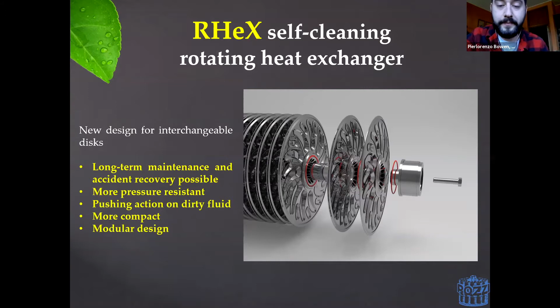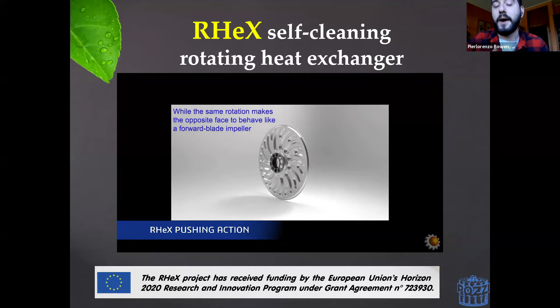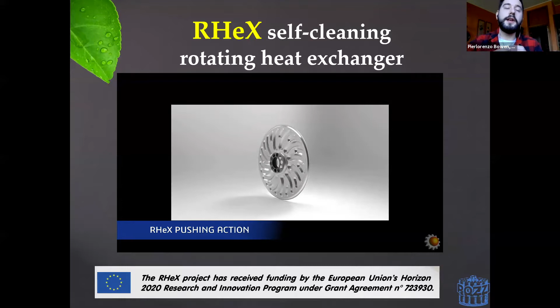Another very interesting feature of our new design is what we call the pushing action. Now, this is due to the geometry that we've created on our discs in the new design. The way it works is that the two sides of the disc effectively act, one as a backwards blade impeller and the other one as a forwards blade impeller. This means that we are creating two different flow velocities on the two sides of the discs.